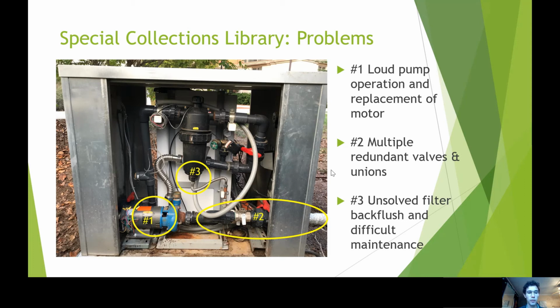Something else to take note of here is that the water from the pump goes in a sort of U shape all around it. And this maybe would not be a problem, but for the fact that the pipes above it were leaking. So all this leaking water was leaking directly onto the pump and motor, causing corrosion. And definitely having water sprayed all over a pump like that is not recommended. A pump is not meant to be in water.